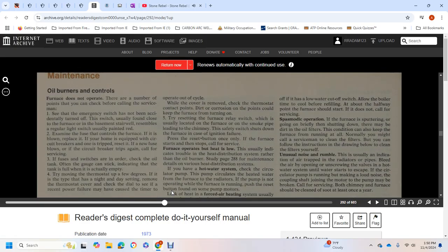Maintenance of oil burner and controls. If the furnace does not operate, there are numerous points you should check before calling the serviceman. First, check the emergency switch, which may have been accidentally turned off. The switch, usually found close to the furnace or at the basement stairway, resembles a regular light switch and is usually painted red. Second, examine the fuse of the furnace control. If it is blown, replace it. If the home is equipped with a circuit breaker, and it has tripped, reset it.